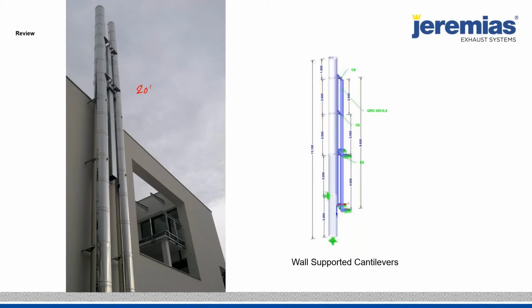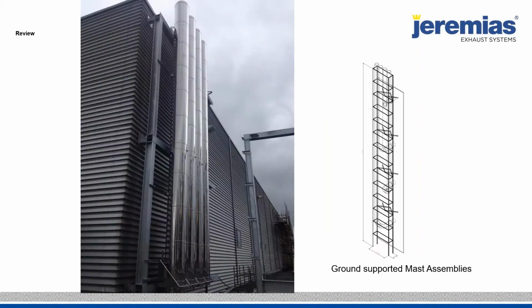Again, the reason behind the 304 stainless outer jacket and all the 304 stainless supports is that the system is maintenance free. These stacks are growing, contracting, expanding all the time. You don't want something that's painted or galvanized or aluminized. Think about specifying a 304 stainless outer jacket. In this case, we designed this cantilever, which is made of stainless steel. We made it in the shop, and we provided the engineer with all the FEAs to show how the system is more than adequate. Here's a data center.